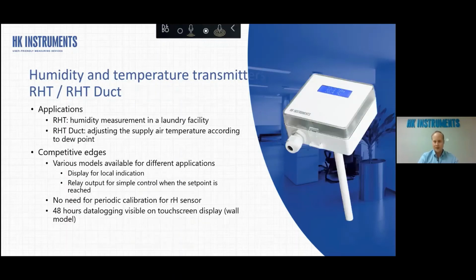And here you can see the picture of the duct model for the RHT. So we have the humidity sensor also mounted to rooms or for ducts. We also have this local display available for this duct model. And the sensor itself doesn't need any periodic calibration. In the room model, this also applies to the CO2 and the humidity, both versions. We have this kind of simple data logging for the display model, where you can see the last 48 hours of data. So you can see if something is wrong in your building with CO2, humidity or temperature, and then make some adjustment to your system.